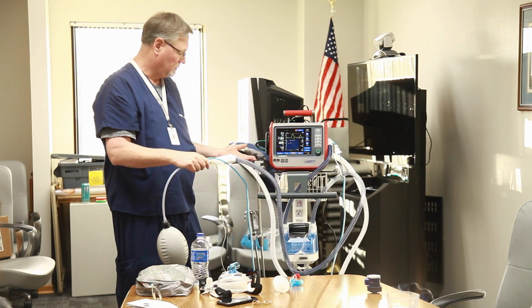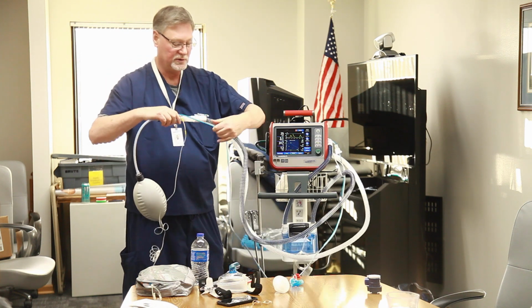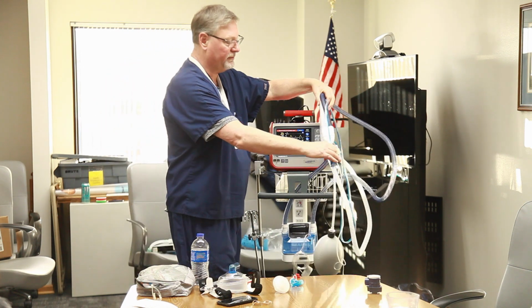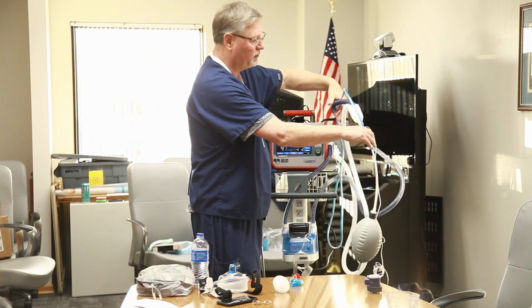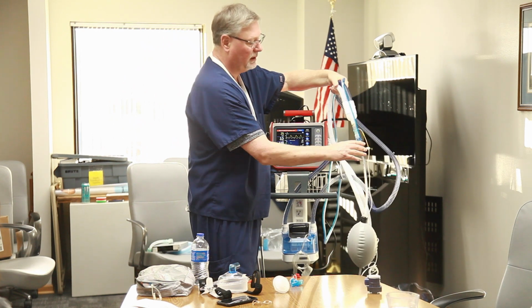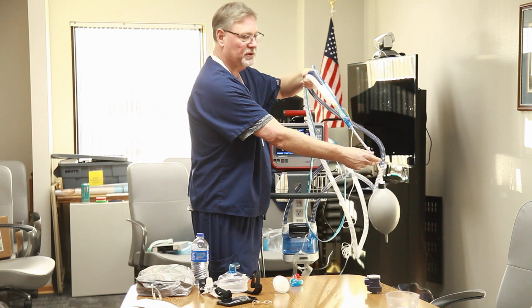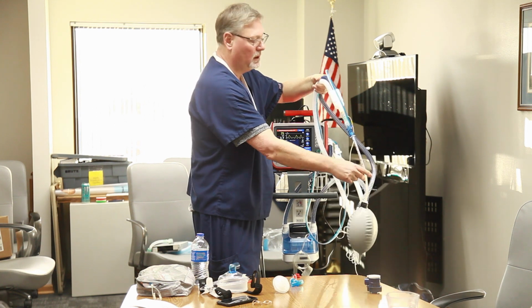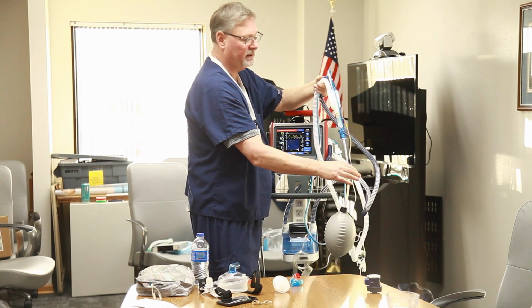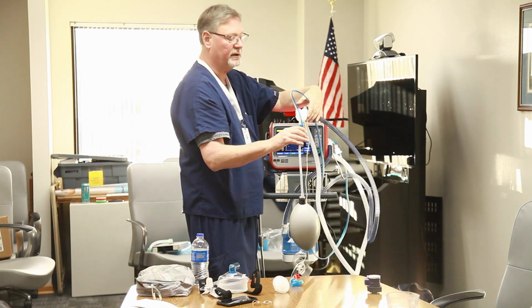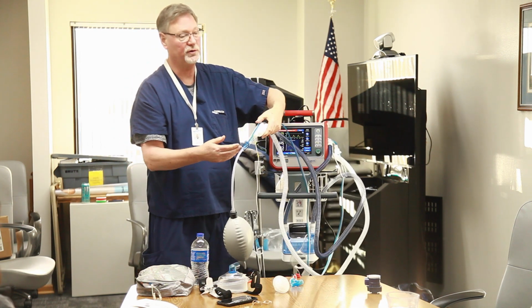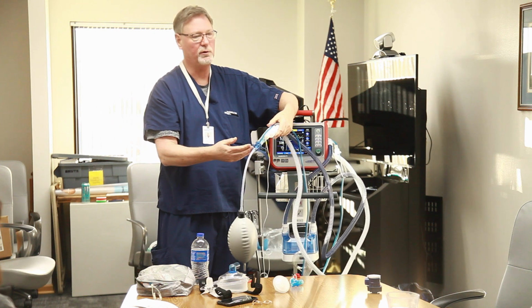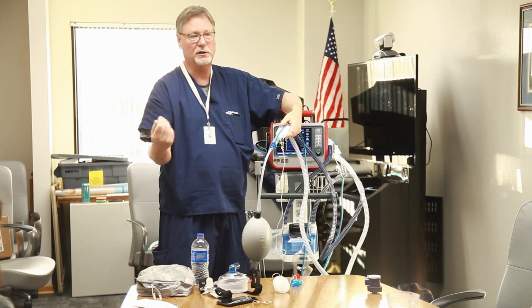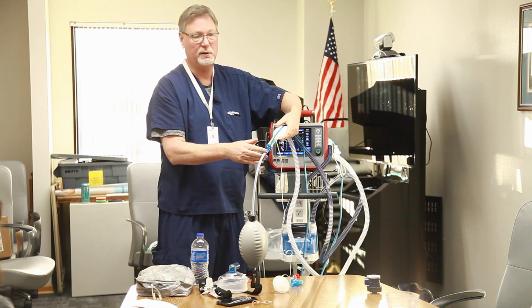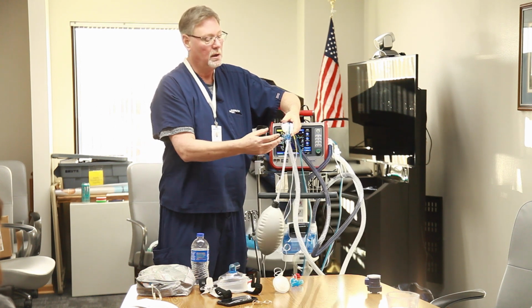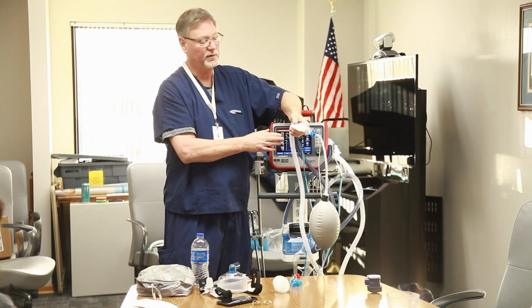You have your tube holder here. Wherever you have your patient, get them nice so everything's sort of angled like this, and this is just going to go right to the ET tube just like this, your flow sensor. Don't put anything on this side of the flow sensor by the patient, other than if you someday decide to get a closed suction system like the Ballard system. You guys don't have that now. Now you just bag your patient, you hook them to suction. You're going to do the same thing with this. Everything should be added on the ventilator side of the flow sensor.